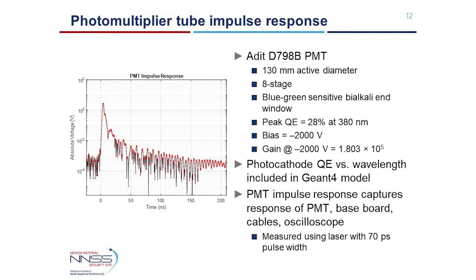We measured the impulse response of the PMT using a 70-picosecond laser perpendicular to and centered on the photocathode of the PMT. This measurement yields not only the PMT impulse response but also includes the effects of the bias board, cabling, and digitizer. The resultant PMT-only impulse response is shown in the plot on the left.